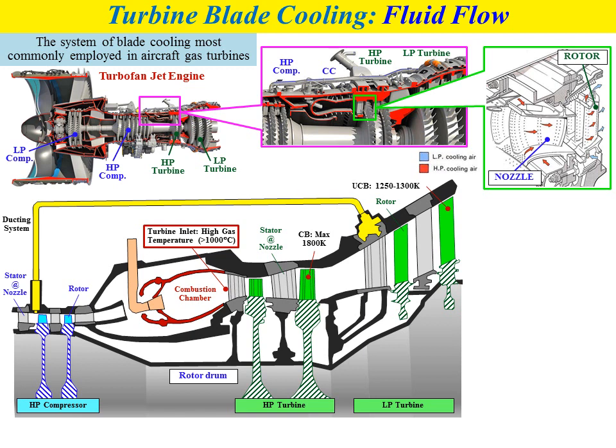However, the cooled blade is used for the high pressure turbine, because normally the high pressure turbine has the highest condition in terms of exhaust gas temperature. For the low pressure turbine, because the exhaust gas temperature is already reduced, the blade type that we use is the uncooled blade, the typical blade without a cooling system. The temperature that can be stood by this blade is around 1250 up to 1300 Kelvin.